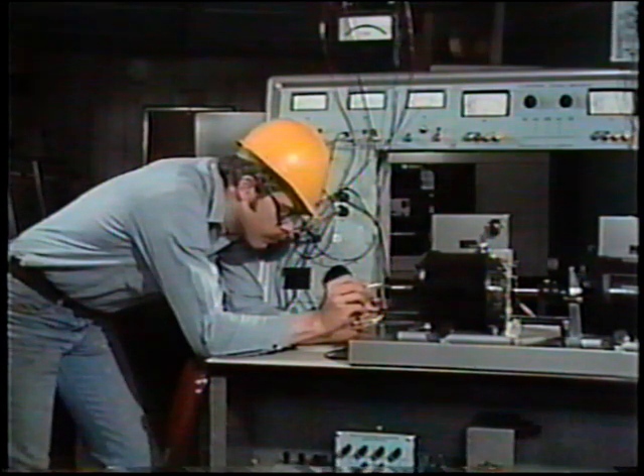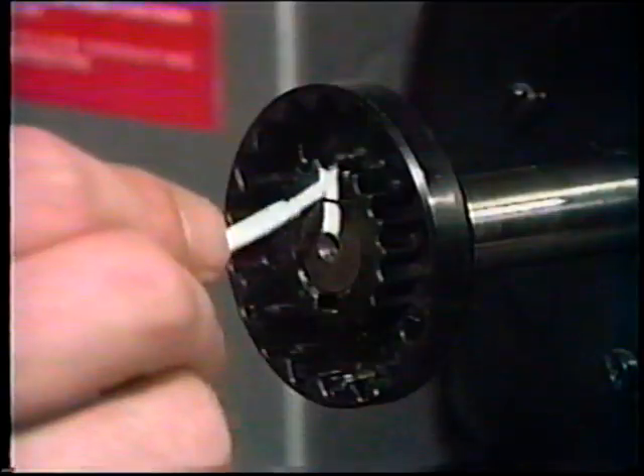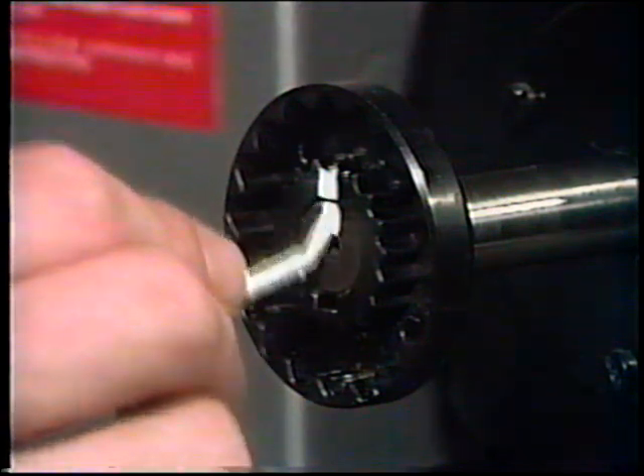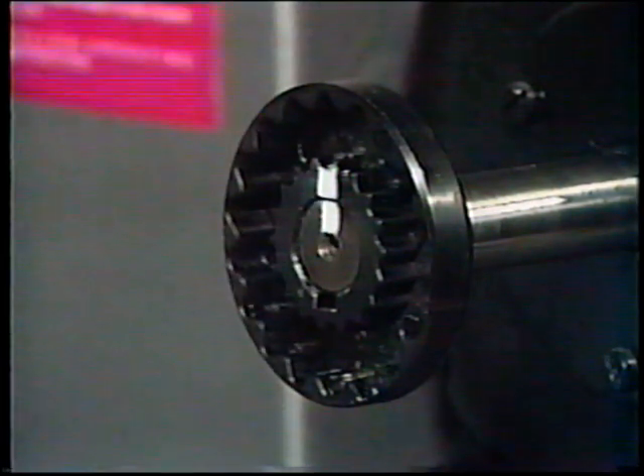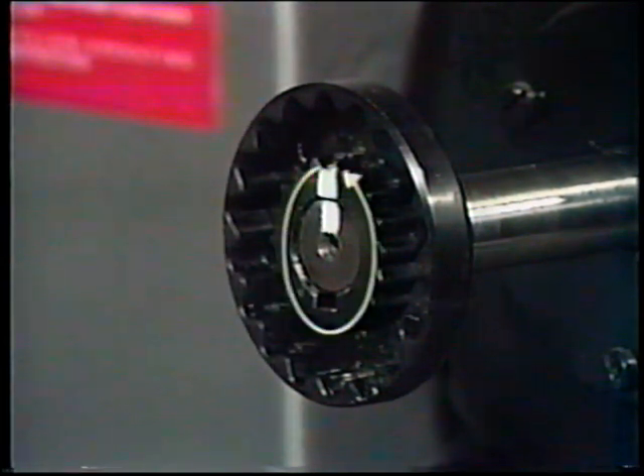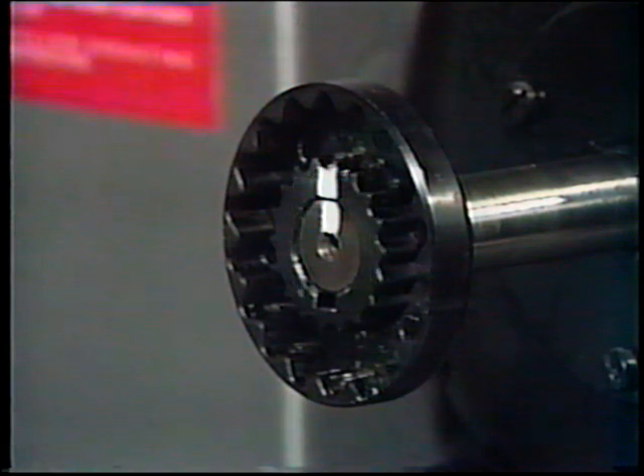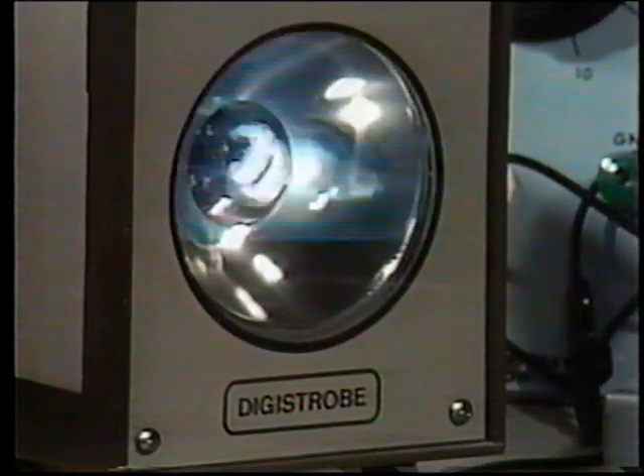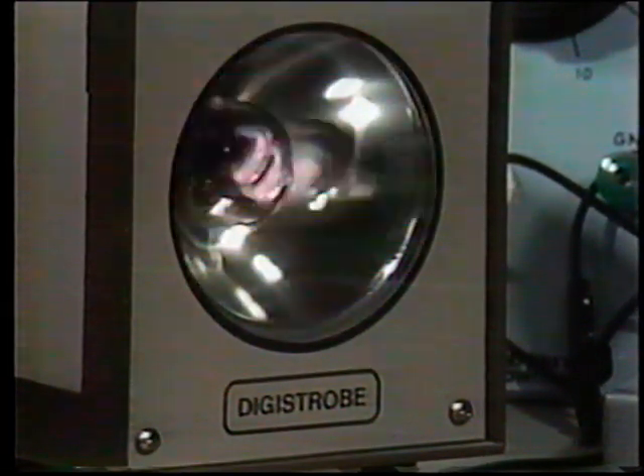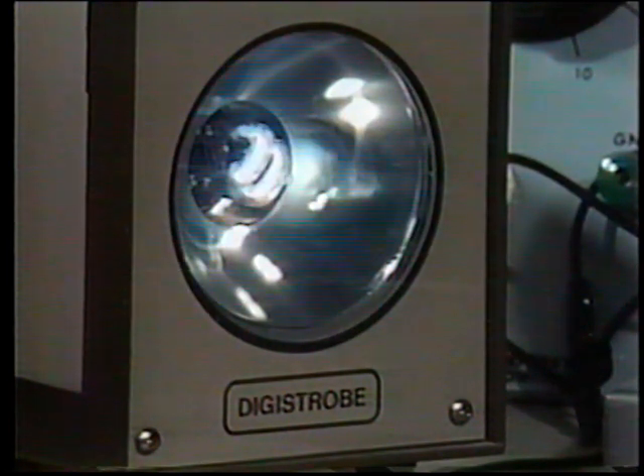We'll mark the shaft of this synchronous motor with white paint. The mark will serve as our reference for rotor rotation. The strobe light will flash on the mark each time it completes one full rotation. When the strobe flashes, the mark will appear to be still. Since this synchronous motor turns at 1800 revolutions per minute, we'll adjust the strobe tachometer dial to 1800 flashes per minute.